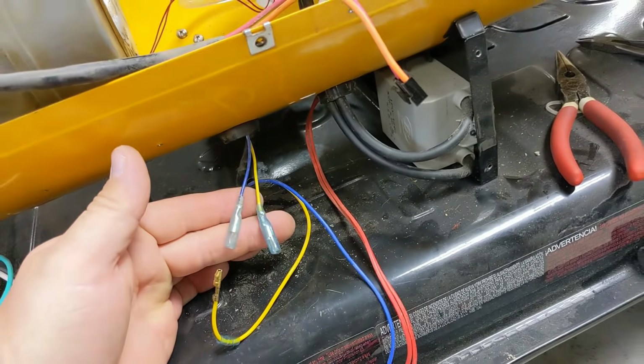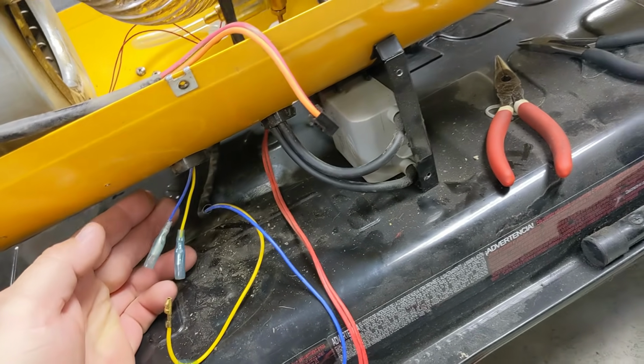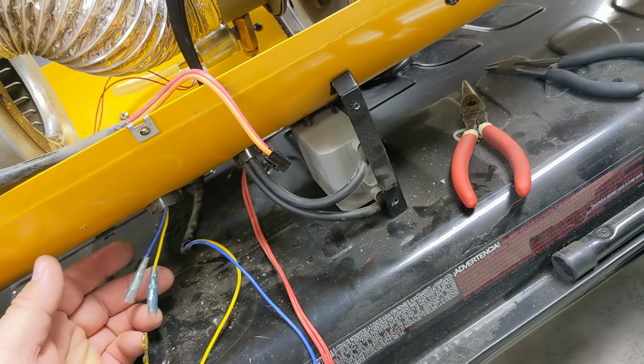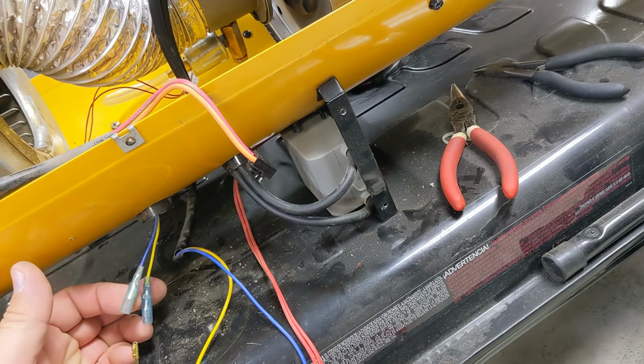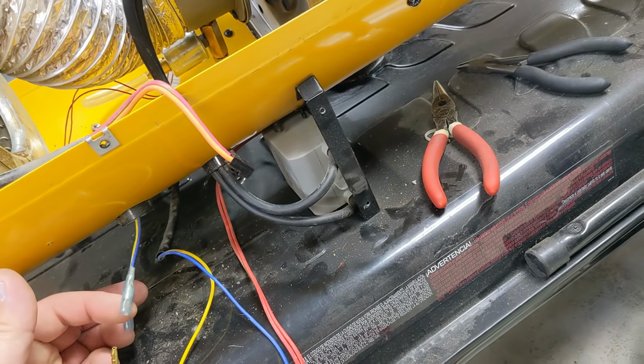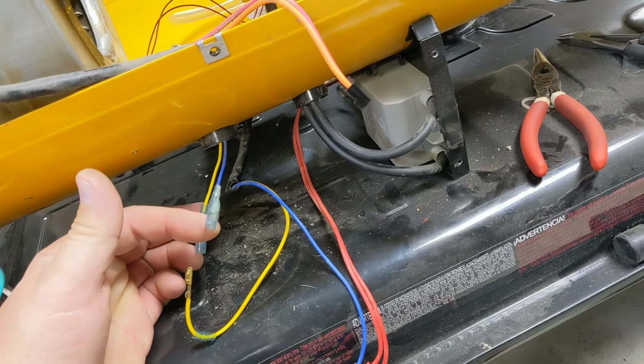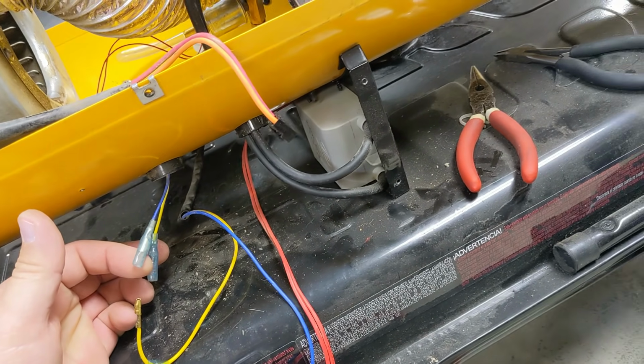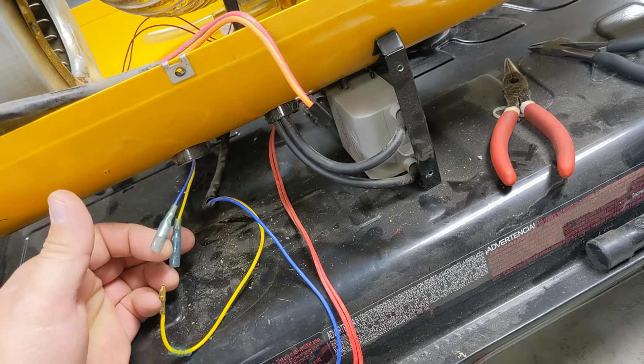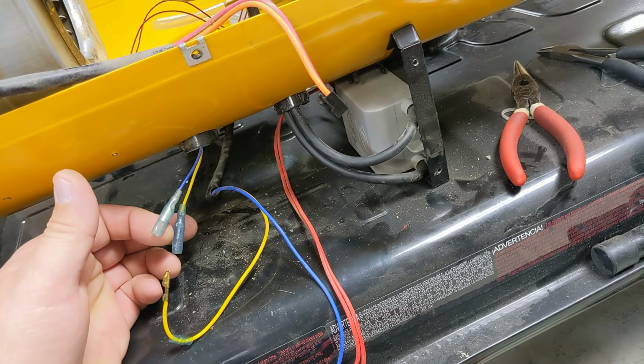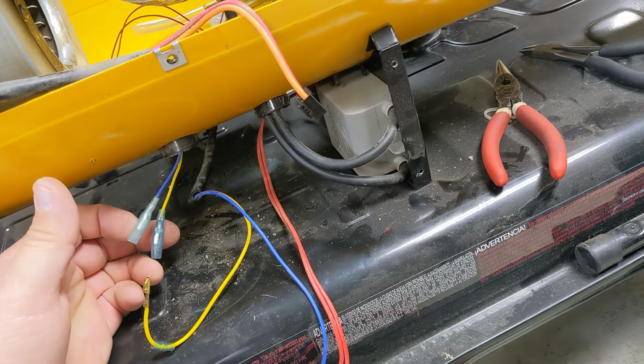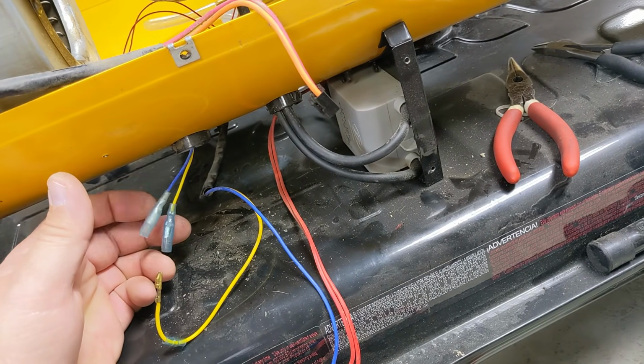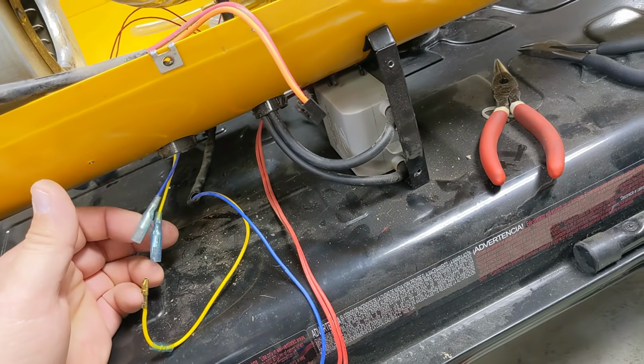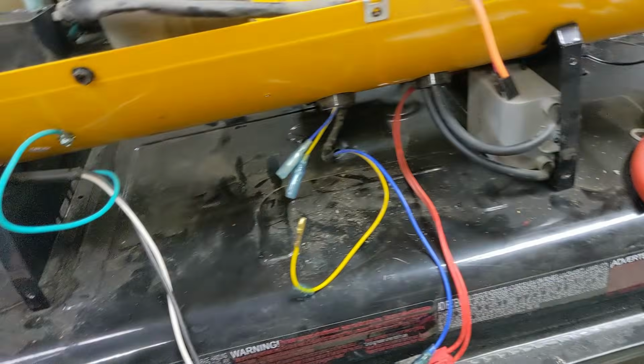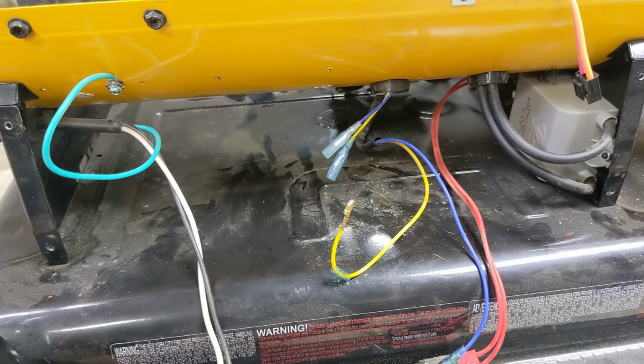So 120 is supposed to come back out of the motor, these two wires right here, and one of them goes over to the pump, just like I said, and the blue one goes through the sensor first, the thermal sensor, and then goes over there to the motor. So that's how the pump motor gets 120 volts, is through the fan connection. But the sensor, I guess, controls running the pump. So let's proceed.